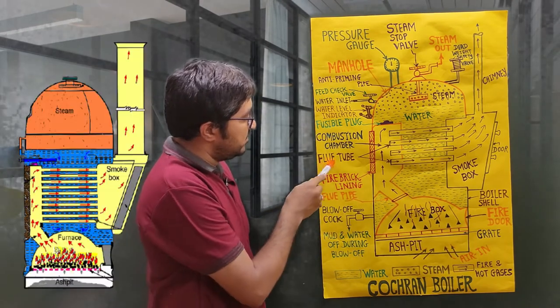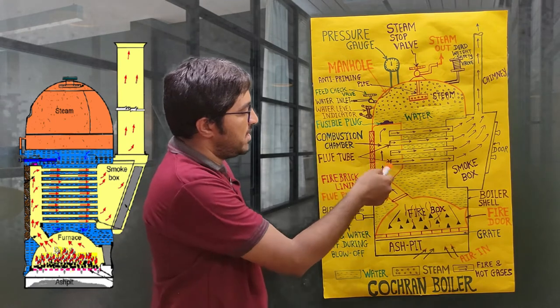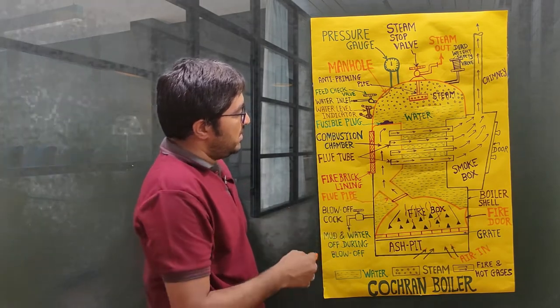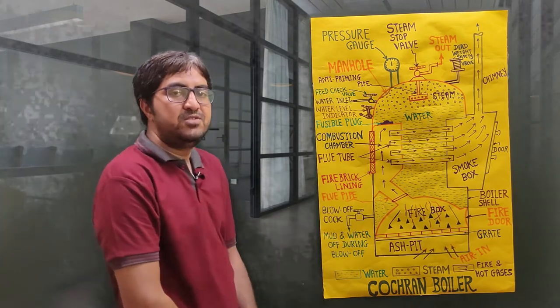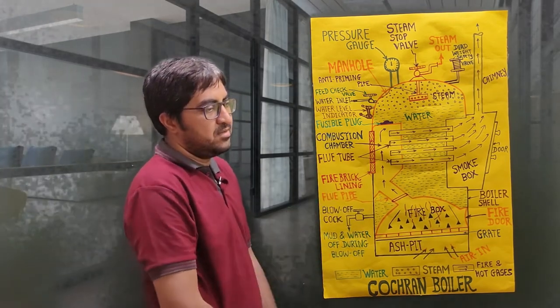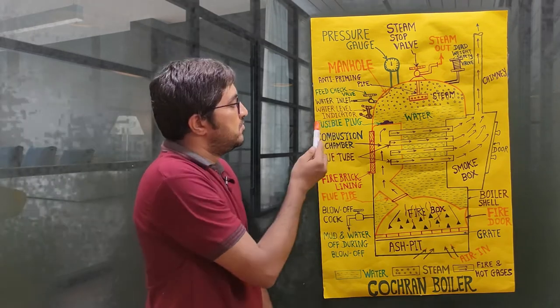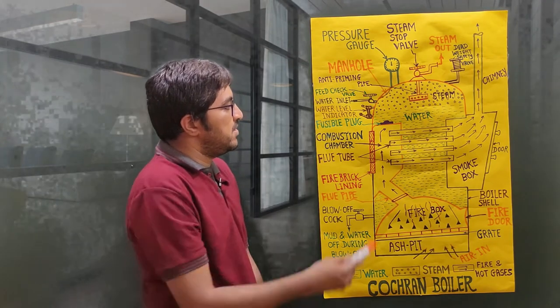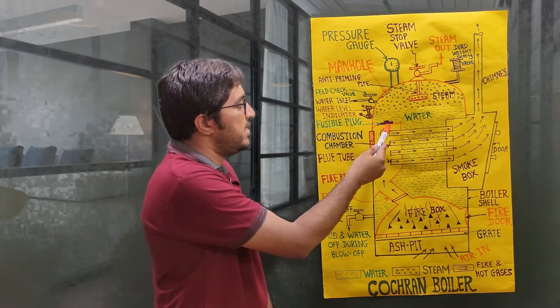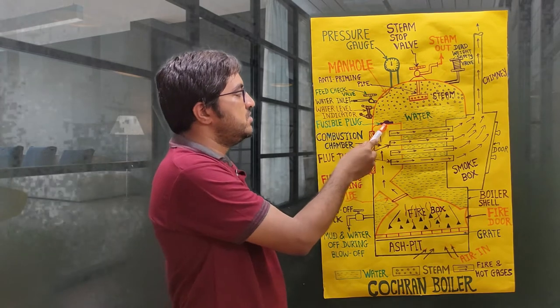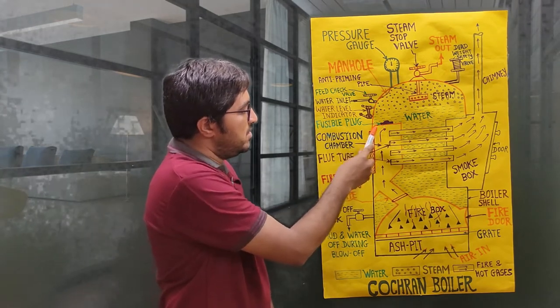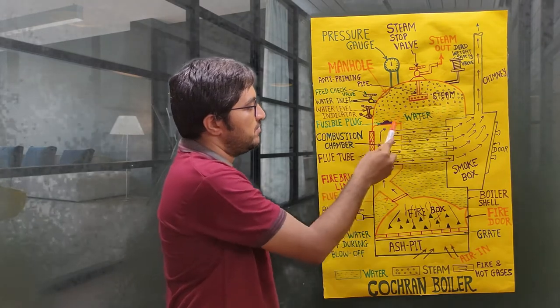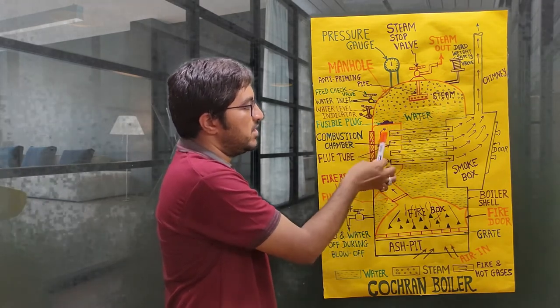The flue pipe has already been discussed — this is an internally fired boiler where flue gases pass through the tubes. The fusible plug is another safety device. Sometimes the main mountings do not operate properly; for example, if the water level indicator fails, the fusible plug provides a backup safety. It is provided on the combustion chamber wall, on the top side of the combustion chamber where there is water above and hot gases below.